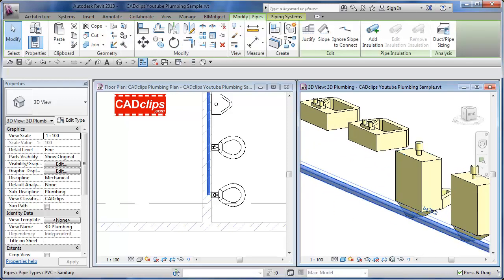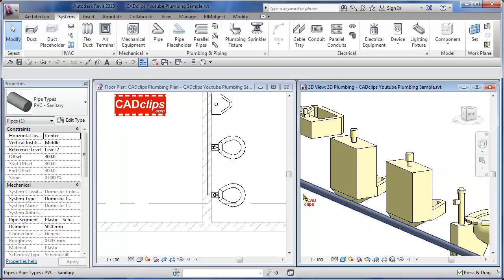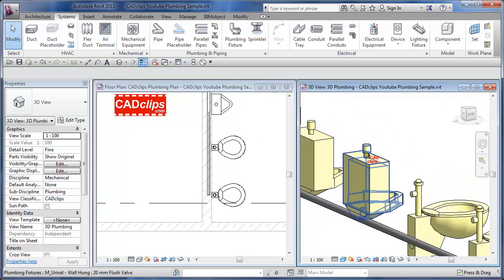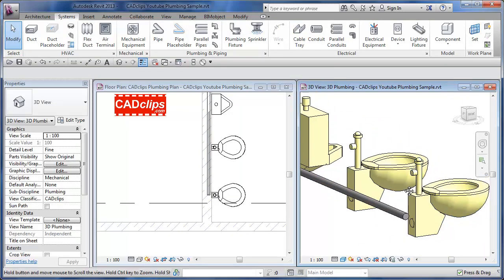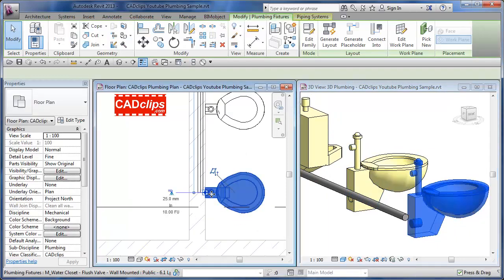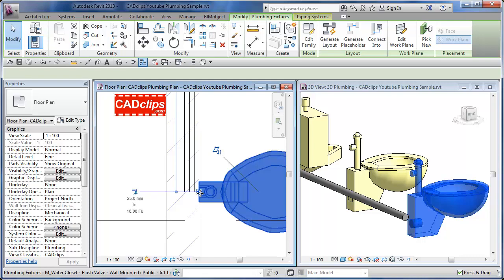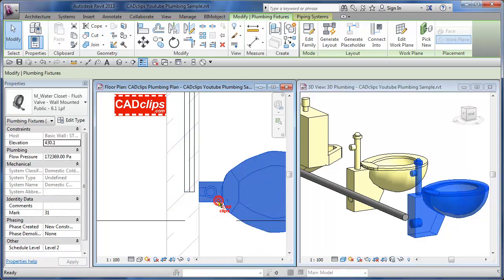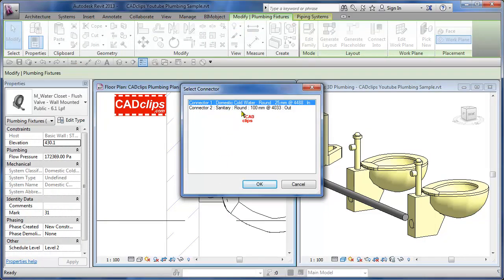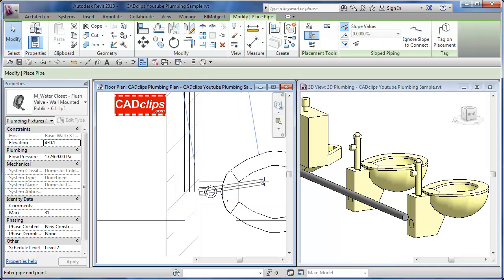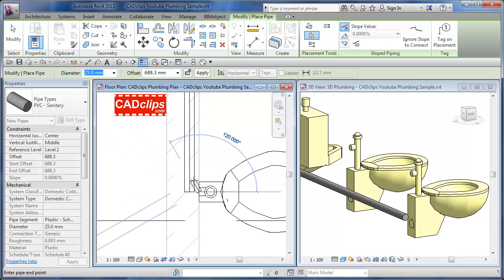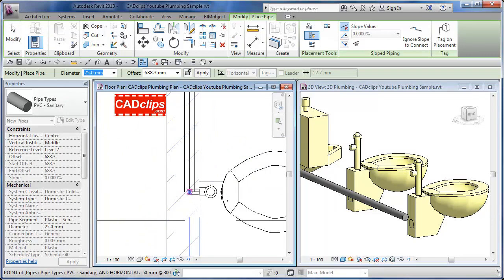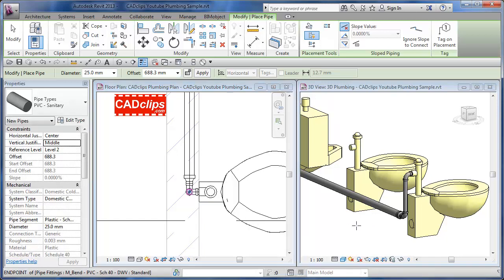So did I make that 100? I meant to make that 50. So then as I go up, I want to now connect that to the cold water here and the cold water supply over there. So I can do this in a 3D view or I can do it in a view from here. Let's say I pick on this water closet. If you right click right on that connector, you can say draw pipe and then from there you can pick, because there's two connectors, there's one sanitary here and one cold water. So I'll say domestic cold water, round 1 inch, 25 millimeters. Then I'll go down and click on there and it's actually going to create that elbow and create that little connection on there.